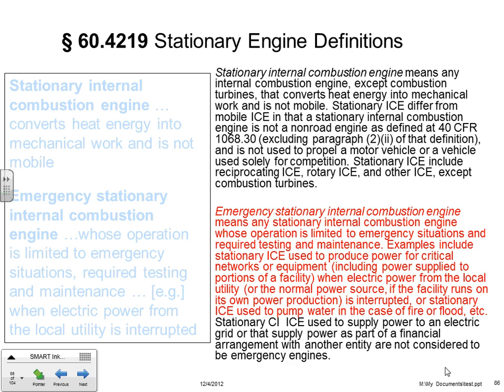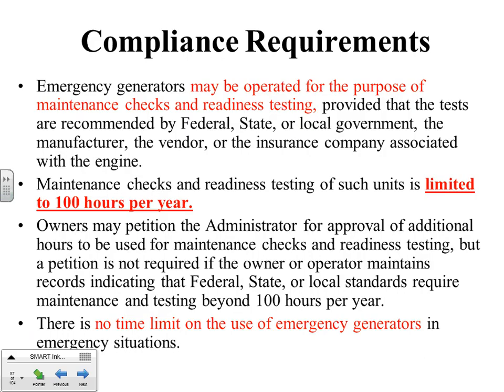Here's the actual code, and I highlighted it in red. This is the definition for emergency now. Emergency stationary internal combustion engine means any stationary internal combustion engine whose operation is limited to emergency situations and required testing and maintenance. So that's the standard definition for emergency. It says that you can run your system basically 100 hours per year, but there's no time limit on the use of emergency generators in real outages. That's why you have the thing.